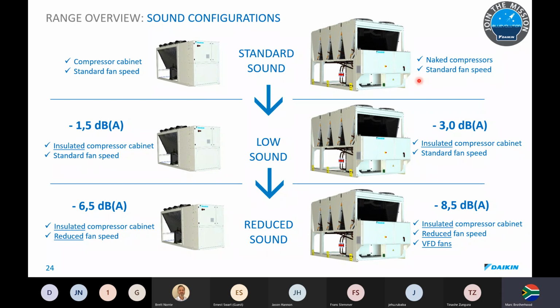In these models, we have obviously the naked compressors, so they're not covered in insulation blankets. They're just exposed to atmosphere. But here we put the compressors in cabinets and we insulate the cabinets. And to get an extra reduction down on these to minus 8.5 decibels, we do all of the above and we put variable frequency drive fans in. This also offers you a much more linear and better head pressure control on your condensing pressure. So besides being quieter, the VFD fans give you a far more linear head pressure control, which means better energy efficiency.